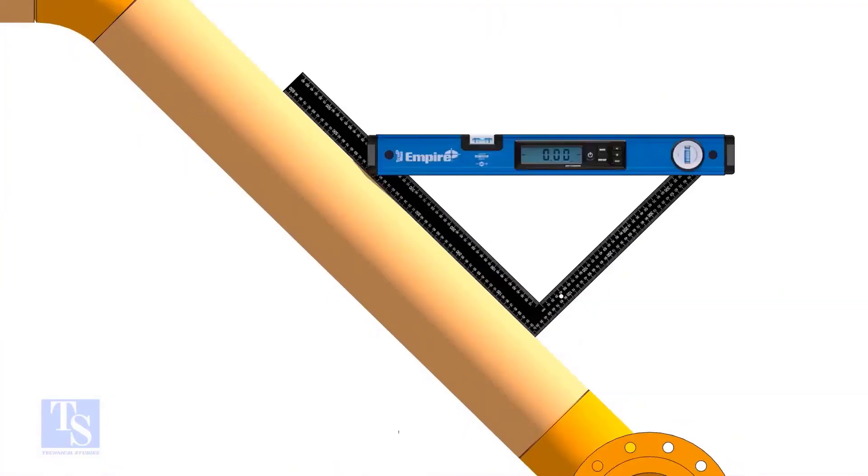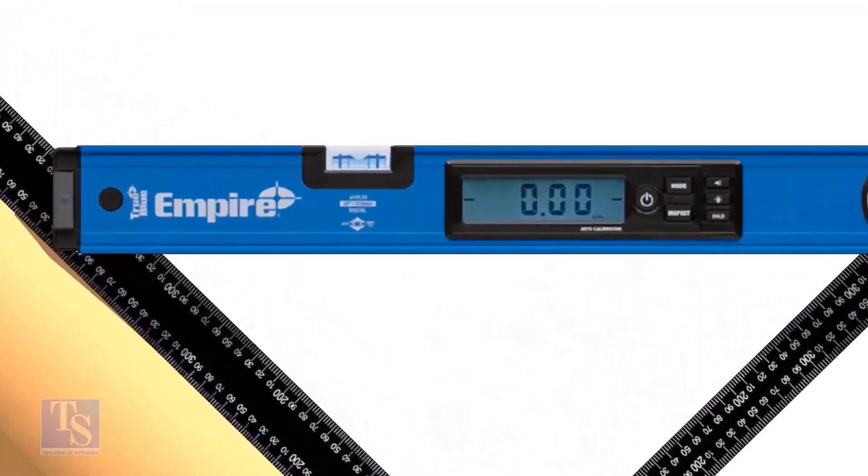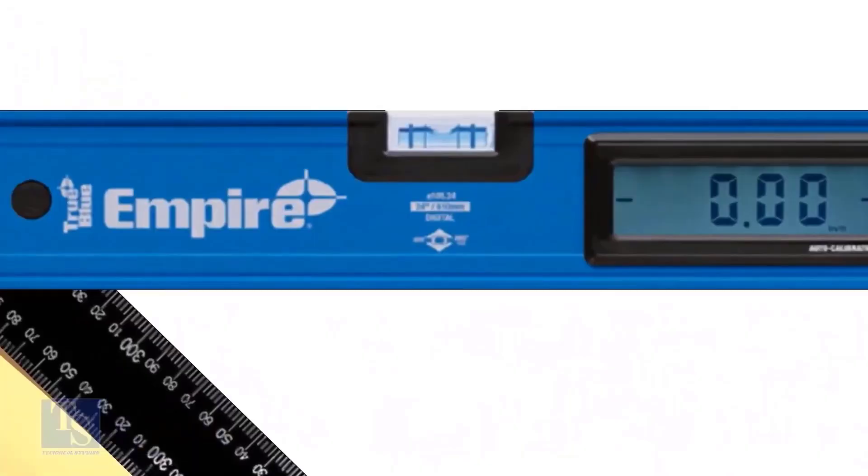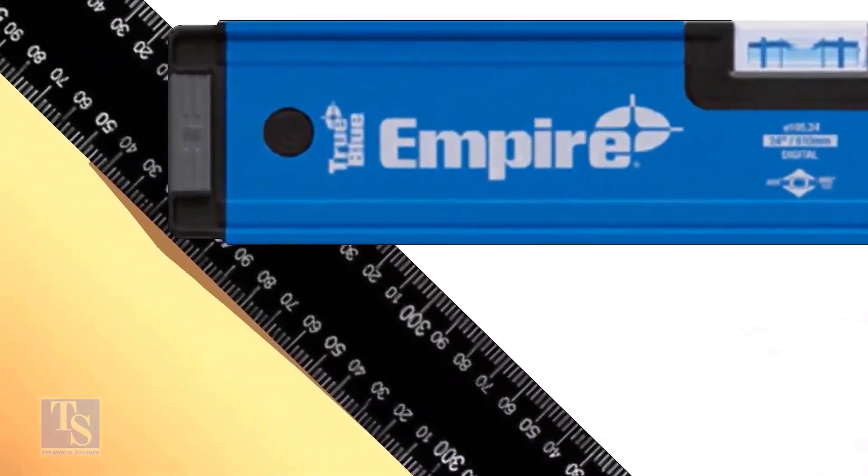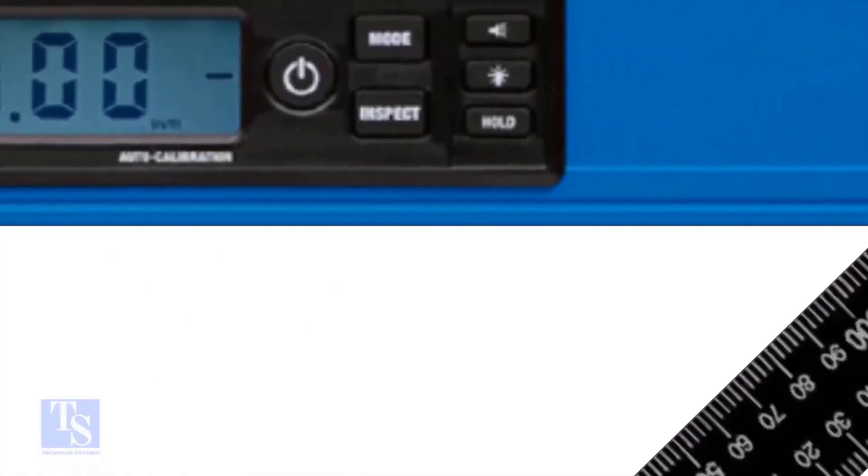Place a large set square or a right angle on the pipe, as shown. Hold a spirit level on the right angle, keeping it perfectly horizontal. Note the readings where the edge of the spirit level touches the unit scale on both sides of the right angle.